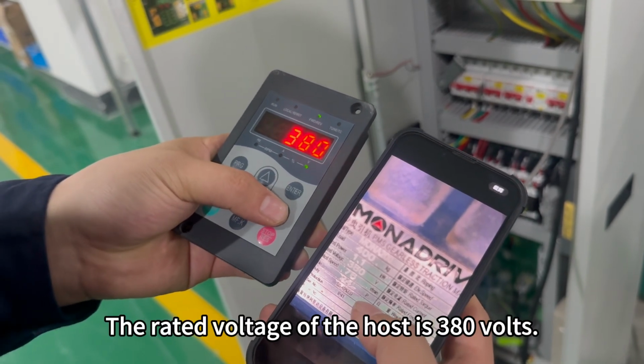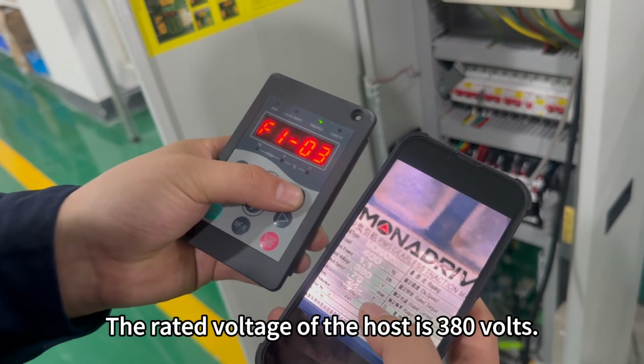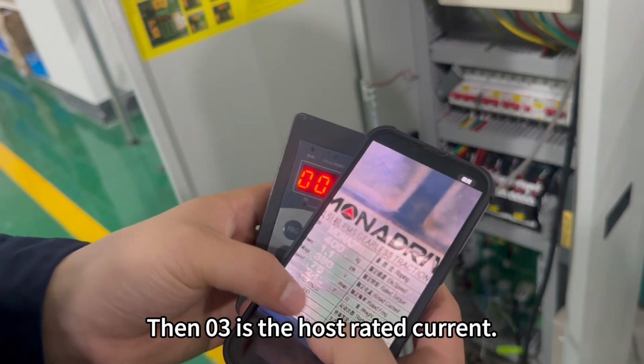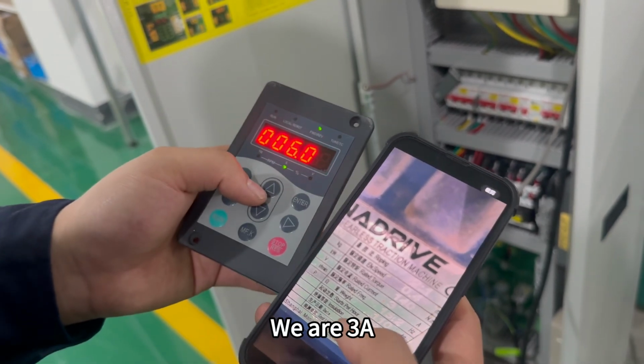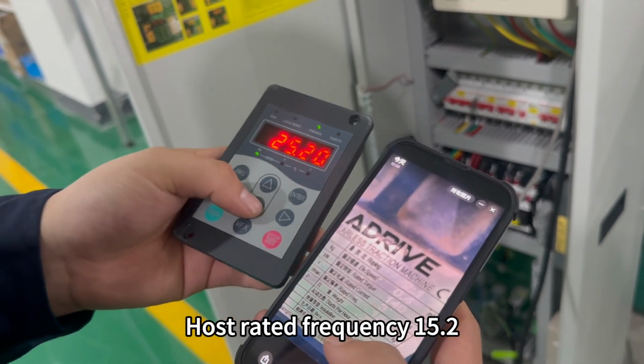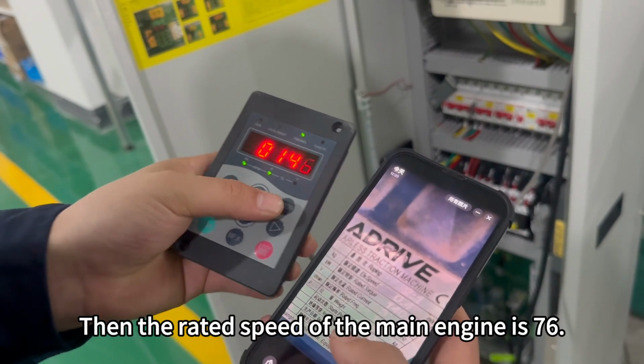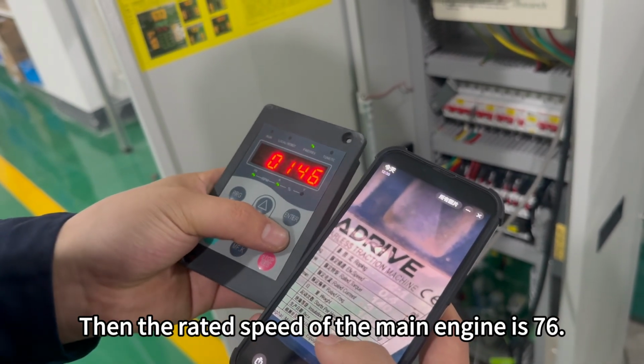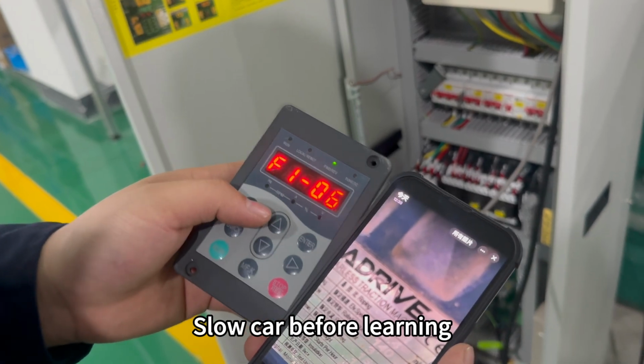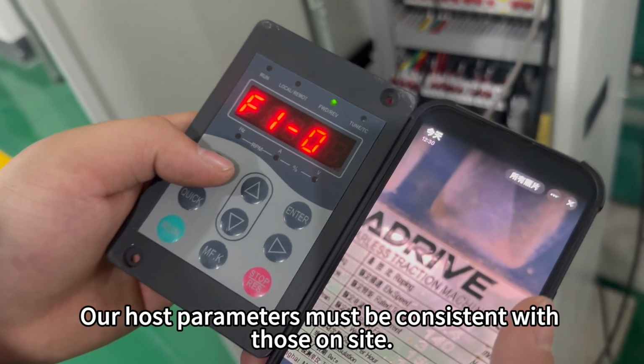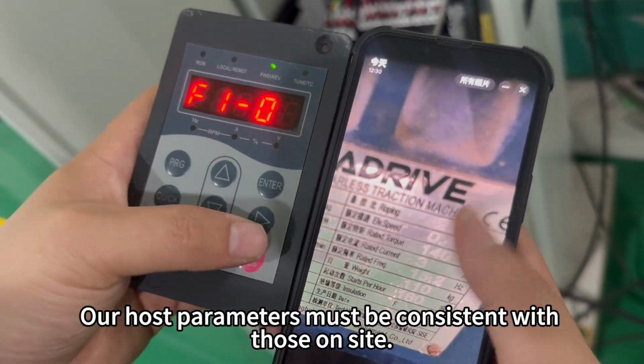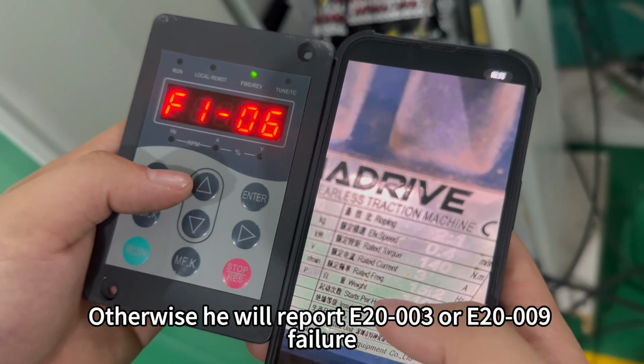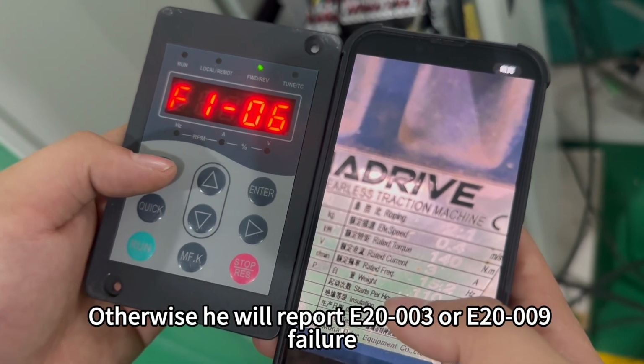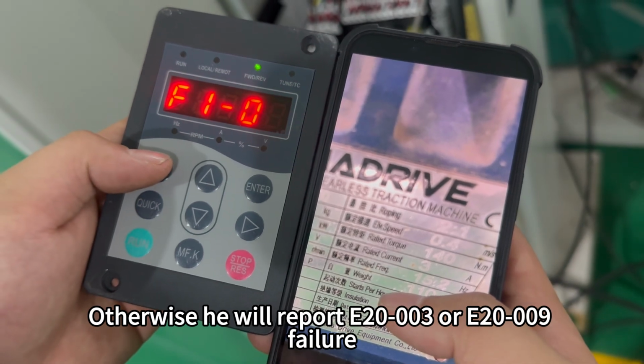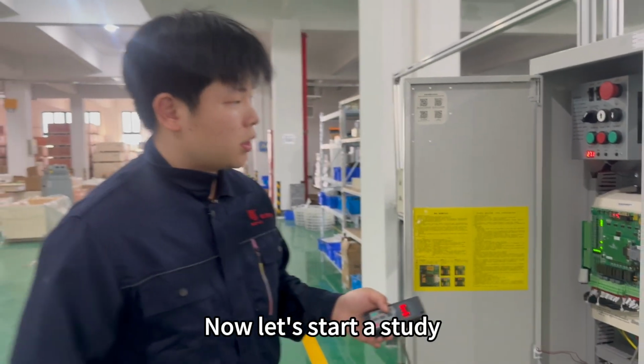The rated voltage of the host is 380 volts. Then 03 is the host rated current. We are 3A. Host rated frequency 15.2. Then the rated speed of the main engine is 76. Before slow car learning, our host parameters must be consistent with those on site. Otherwise, it will report an E20-003 or E20-009 failure. Now let's start the study.